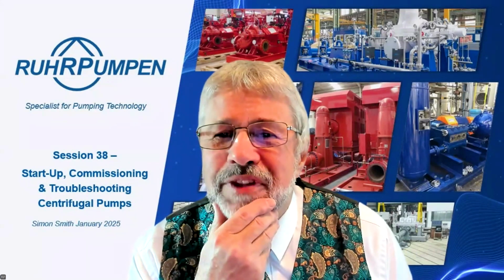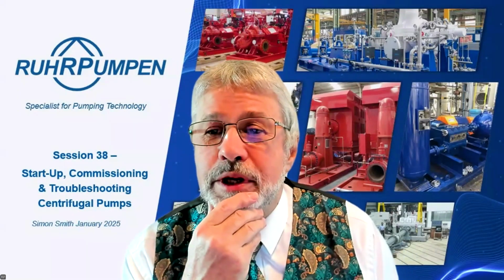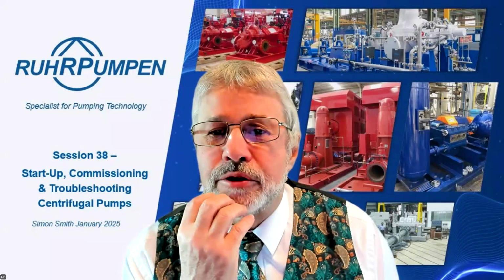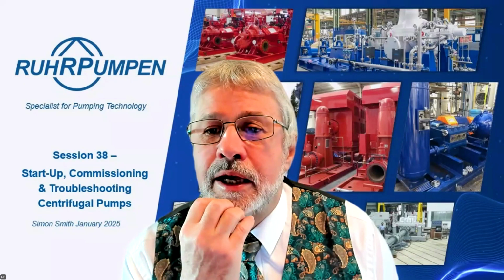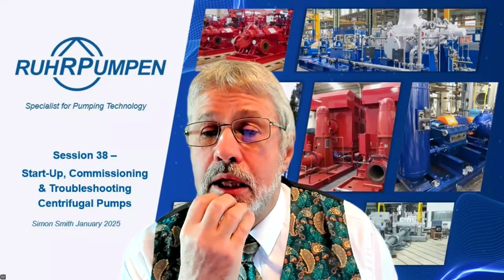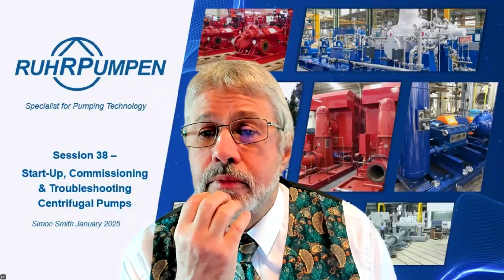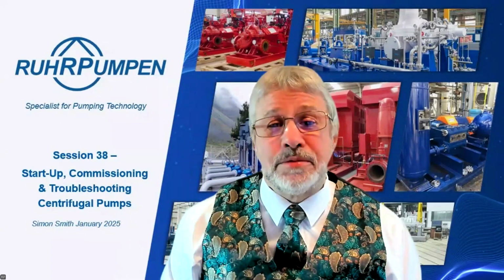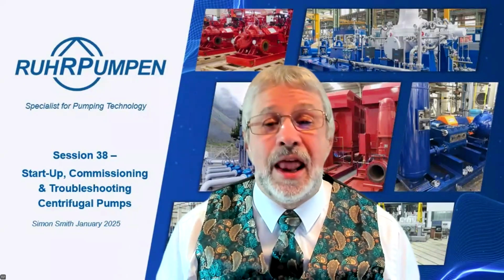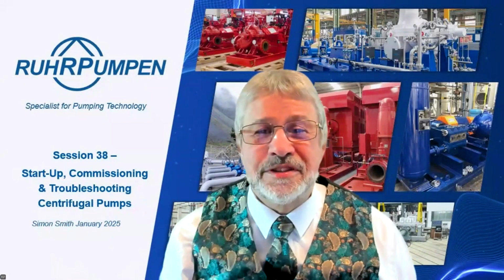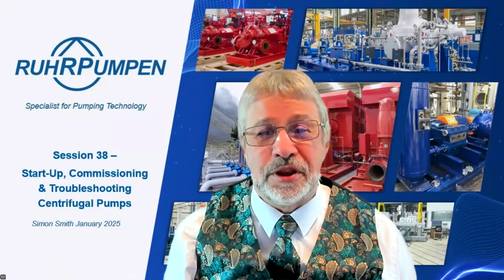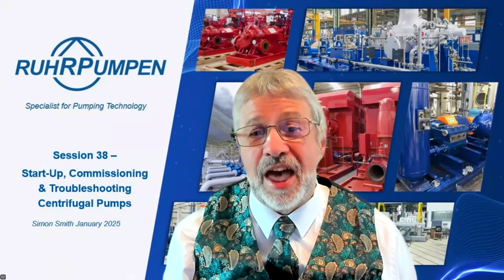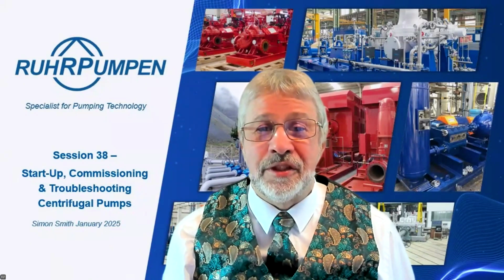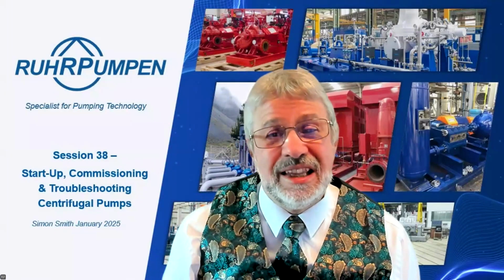Customer needs flow margin, usually can be 20%, and use a throttle valve to reduce this. How great can this margin be? Virtually every pump spec has built-in safety margins, so it's not unusual for the rated condition to be 20% higher than the actual position. This is okay.